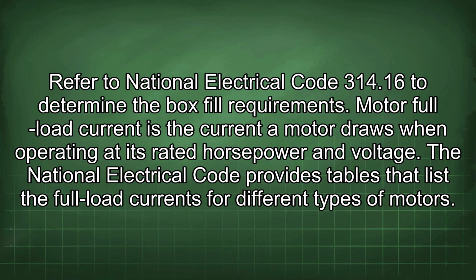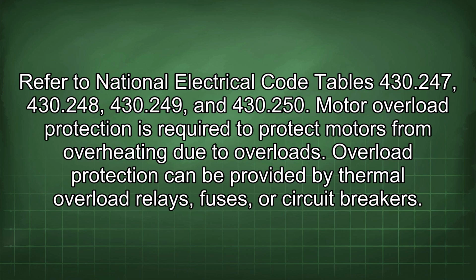Motor full load current is the current a motor draws when operating at its rated horsepower and voltage. The National Electrical Code provides tables that list the full load currents for different types of motors. Refer to National Electrical Code Tables 430.247, 430.248, 430.249, and 430.250. Motor overload protection is required to protect motors from overheating due to overloads.